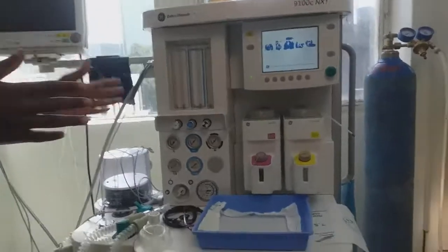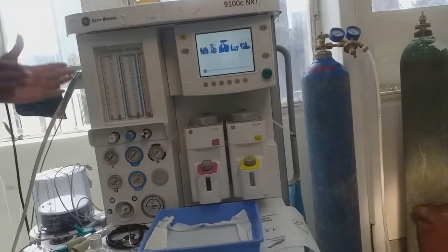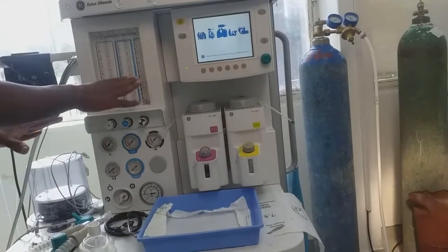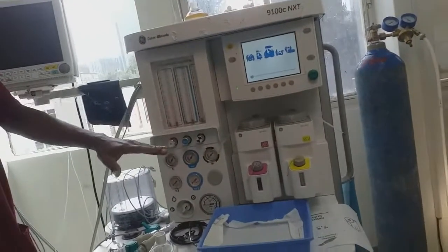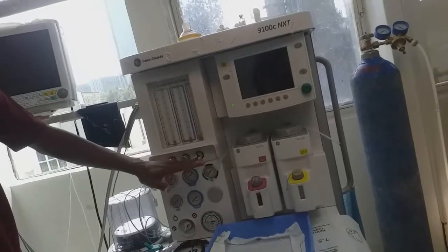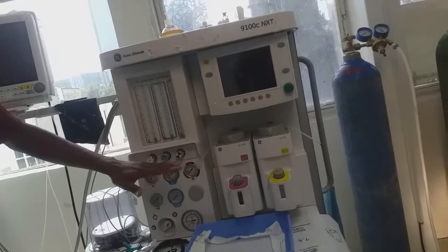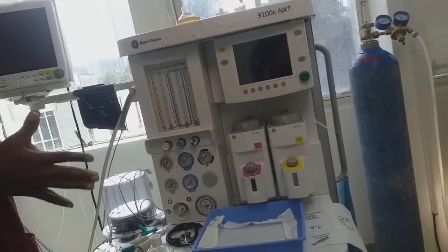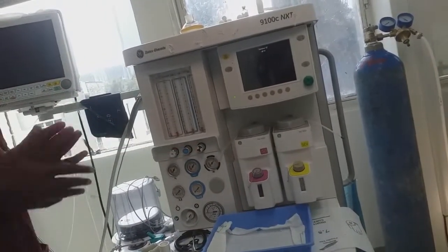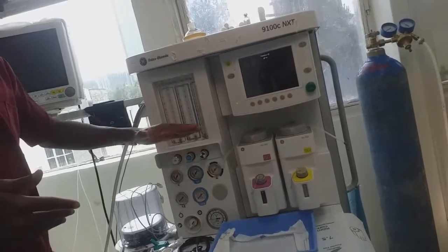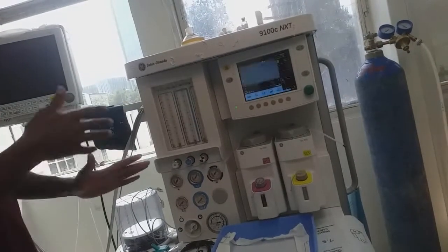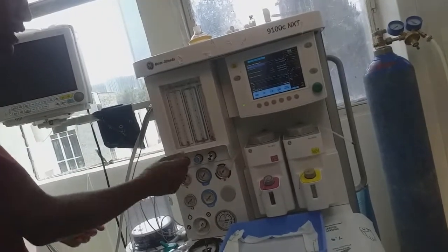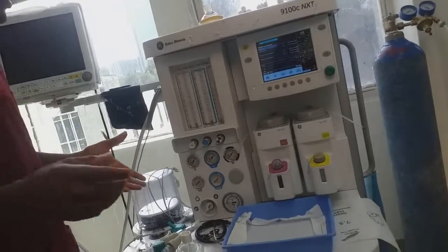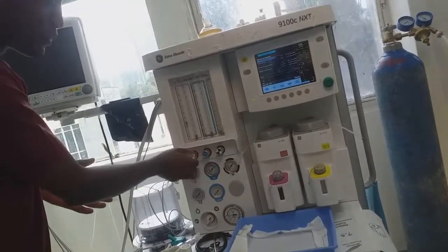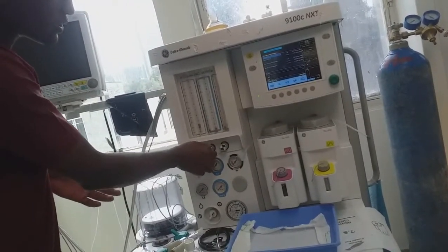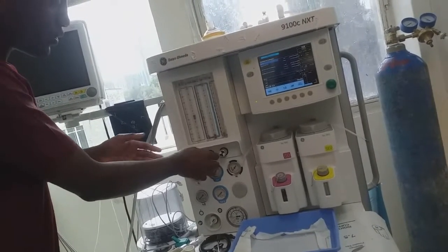Now to check the low pressure system, we need to check whether there is any crack on these flow meters or in their arrangement. The arrangement also matters. Oxygen should be the last gas. We need to see whether the arrangement is correct. And there is the anti-hypoxic device. The anti-hypoxic should be checked. If we open only nitrous oxide, oxygen should open as well.